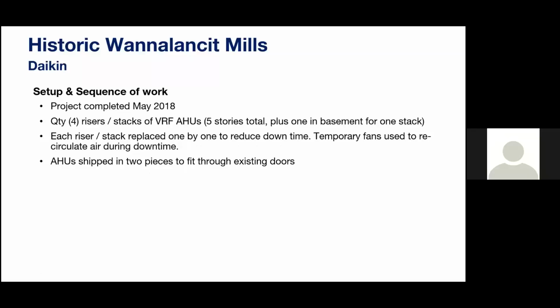In terms of the overall piping design, we have 4 risers or stacks of VRF air handlers on this 5-story building, with 1 riser going all the way down to the basement. To make it simple during the install, we replaced 1 riser at a time to reduce the downtime and interruption of the tenants that were still in there while making these modifications. Then we would run some temporary fans to just keep the air moving during any downtime as well.